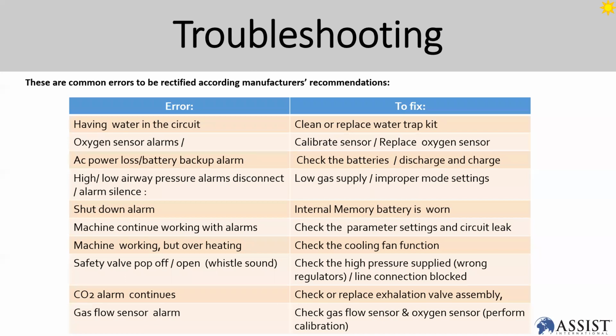So, troubleshooting. When you talk about troubleshooting, there are a lot of things that you need to look into. Always make sure the water trap is clean, and replace it if needed. Then the oxygen sensor alarm: you need to calibrate the sensor or replace the oxygen sensor. Then the backup battery: check the battery, discharge and charge. If still not working, you need to replace the battery. Then high and low airway pressure alarm: make sure your gas supply is properly connected with the right pressure. Your mode of setting of your system can also cause a lot of alarms.